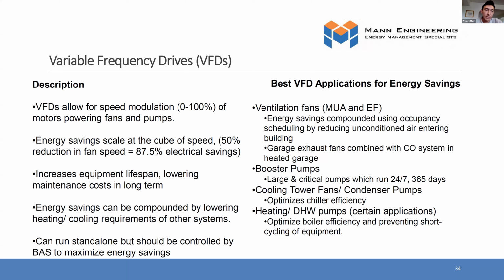Like I said, with the example of the makeup air, not only are you saving on the electrical consumption of the fan itself, but you're also saving heating costs, right? So ventilation is a great application for VFDs, because we can put the fan on an occupancy schedule. That's typically done through the BAS, so you'd want to have an integrated control solution here. But basically, the building's not fully occupied all the time. People go to work during the day.